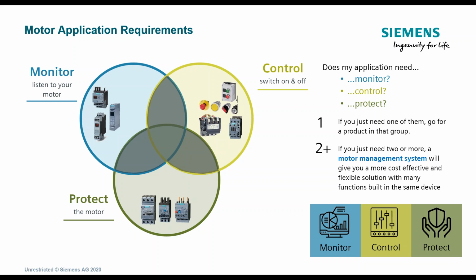And then, of course, you want to monitor. Monitoring is a key thing for motors. The key for that is that motor application, your process engineer is a data hungry person. You can't improve a process unless you measure. And so you can listen to your motor to what's going on. That could be a temperature on some bearings, or it can be vibration with misalignment. It could be many things that we will investigate today with SIMOCODE.